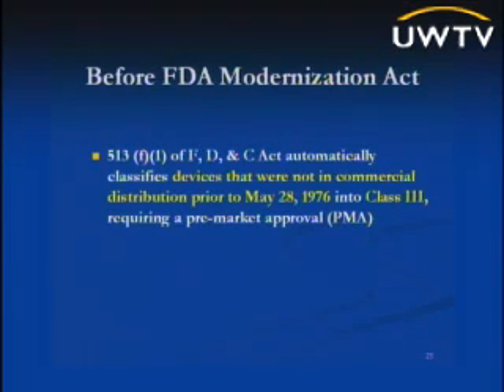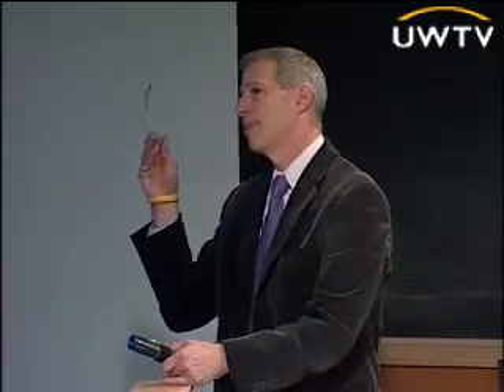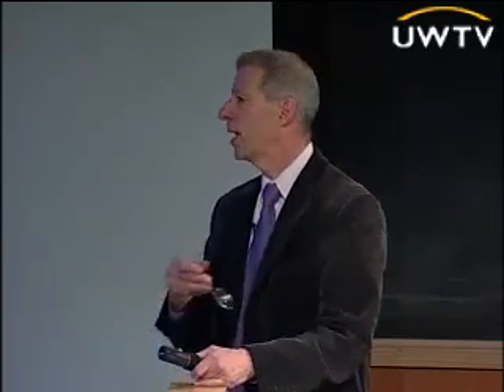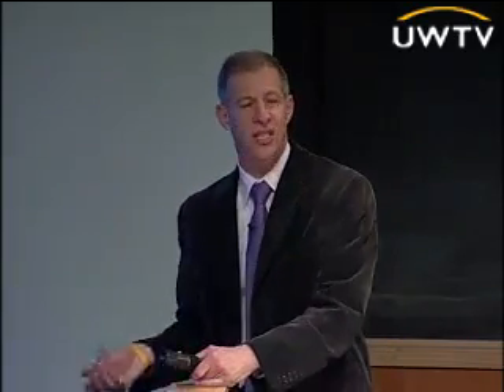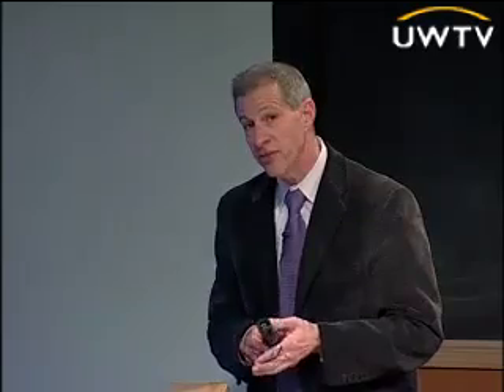The IDE is required. And before the FDA Modernization Act of 1997, I apologize, and now we're getting into the other pathway, de novo, this part of the Food, Drug, and Cosmetic Act automatically classified devices that were not in commercial distribution prior to 76 into Class 3 requiring pre-market approval.